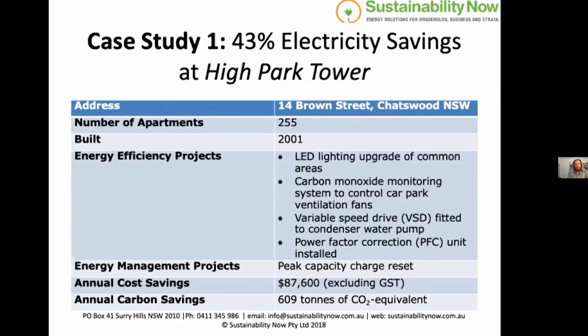The pump was found to be oversized for its application and was providing pressures far higher than were necessary throughout the pipe work. So that was able to be wound down significantly, and also wound down again in winter when it wasn't used as much. This building also installed a power factor correction unit as well that saved them quite a lot of money.